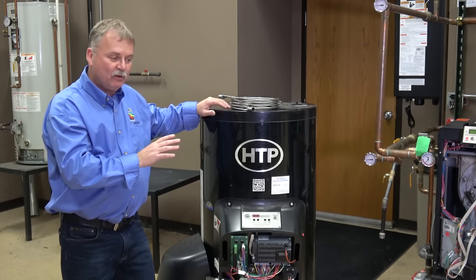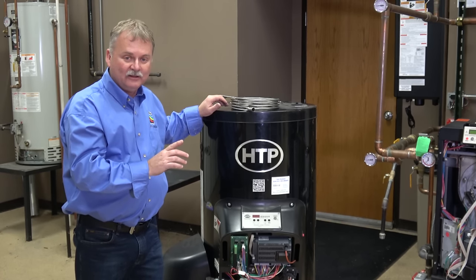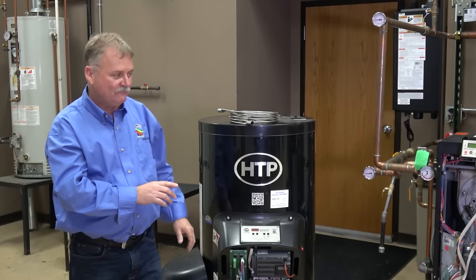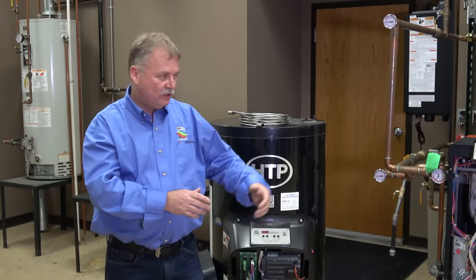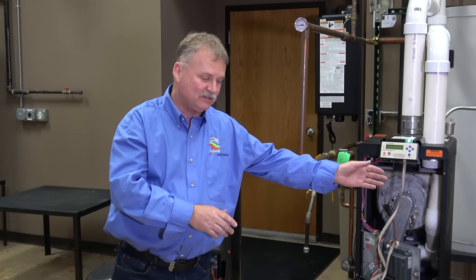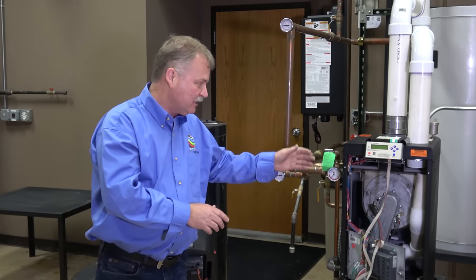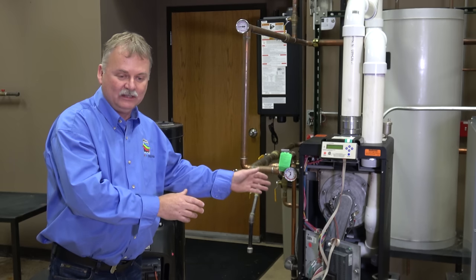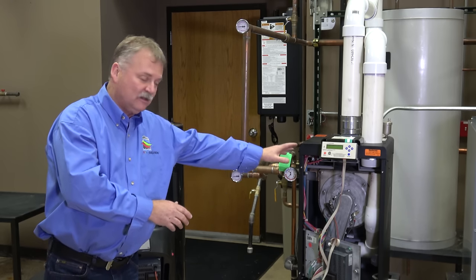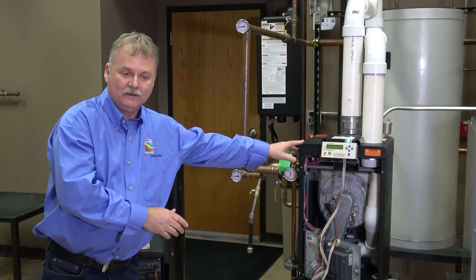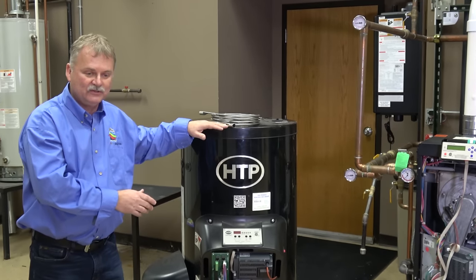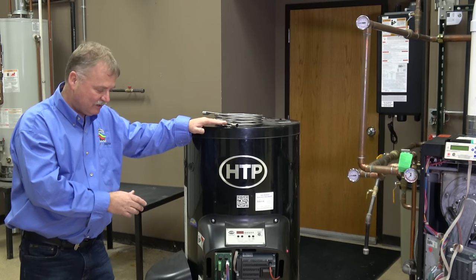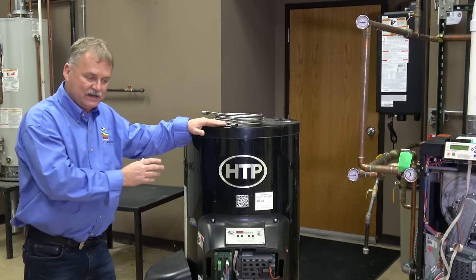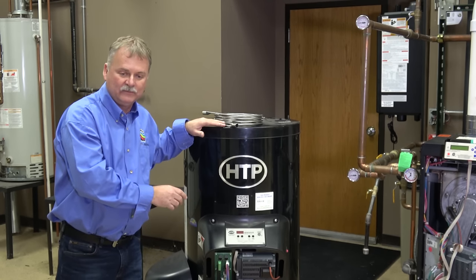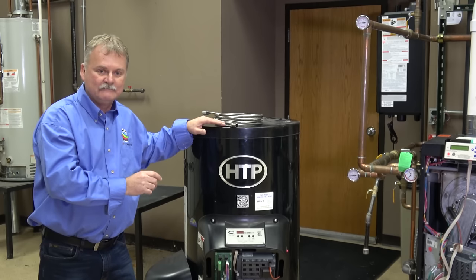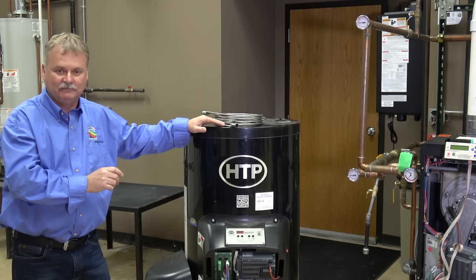So there is no perfect boiler in the world. If there was, we'd only be selling one. Okay, but there's not. You've got to look at your application. You've got to look at what you're trying to do. If you're looking for a low cost, simple installation, simple system, probably your cast iron is going to be your best bet. If you're looking for a smaller system, high efficiency, you don't have a lot of zones on it, not a lot of small stuff, maybe a low mass, high efficiency boiler would be your best bet. If you're looking for something that has a lot of small zones, six flats, multiple apartments, that kind of stuff, you don't want to cycle the boiler, now your high mass, high efficiency boiler would be your best bet. So always look at your application before you pick a boiler. There's not one that covers everything. Thank you.